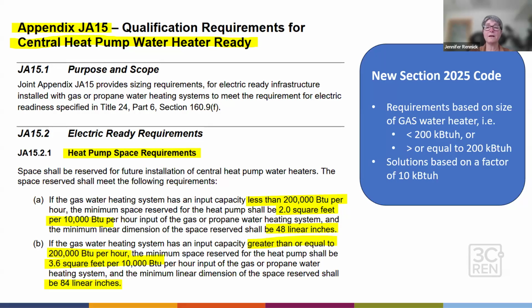The requirements are based on the size of the gas water heater that's being installed. And it's really, if it's less than a 200 kBTU per hour unit or more than or equal to the 200 kBTU per hour. And then each of these requirement solutions are based on a factor of 10 kBTU per hour of installed capacity. So the cutoff there is basically like, okay, if it's a small system or a larger system.